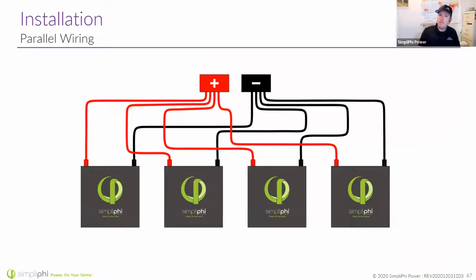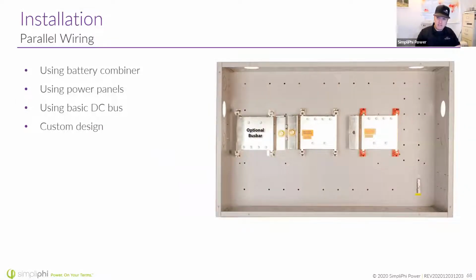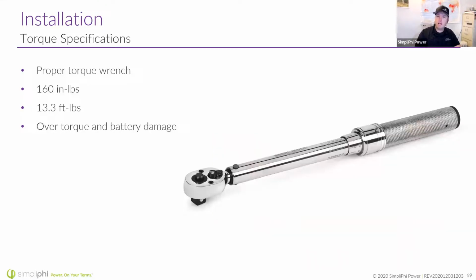When you're wiring batteries, it's important to understand that we never wire our batteries in series, always in parallel. For parallel connections, we want conductors of the same gauge and the same length going from the batteries to a common terminal point, like a bus bar or a combiner box, and then from that piece of equipment up to the inverter and the charge controllers. That way there's no impedance imbalance in the system and each battery is working just as hard as the next. That's the Midnight Solar 1000 amp combiner you see in that picture. We also have our own bus bars, which you'll see here. They were in the previous pictures, and I can point them out in a second as well.